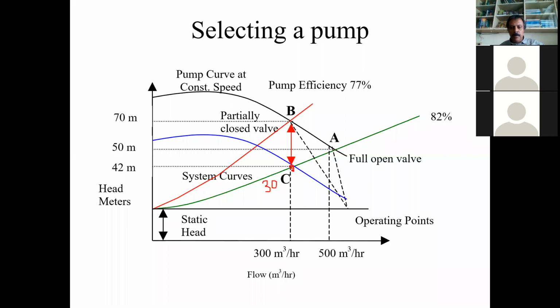So now, at 300 meter cube, the option of going for a smaller pump gives you 30 kilowatts. Otherwise, it would have been 45 kilowatts with throttling. Instead of a smaller pump, of course, you have bought a big pump, you can't change it for a smaller pump. So you trim the impeller, or take out the impeller and keep it in the store, buy a new smaller impeller and put it inside the casing. It will be this blue curve.